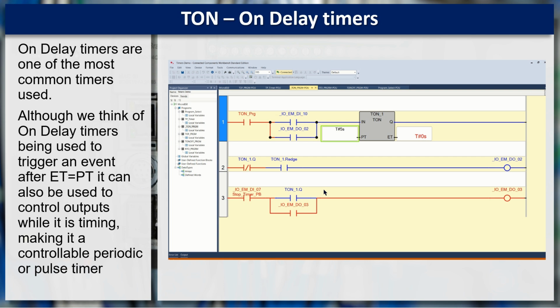So I'm going to reset digital input 7 by turning it off. Okay, so that digital output's through. So let's prove that TON1.Q is actually doing its job. So I'm going to press the start button, and this only seals in because this had to have been true. It flashed on for a second and it dropped out. Every time the IN drops, the TON timer will stop.